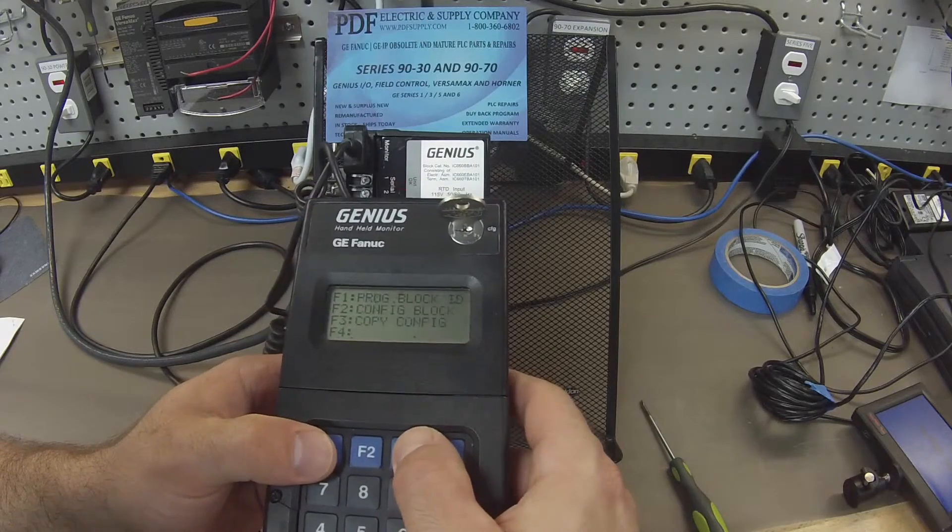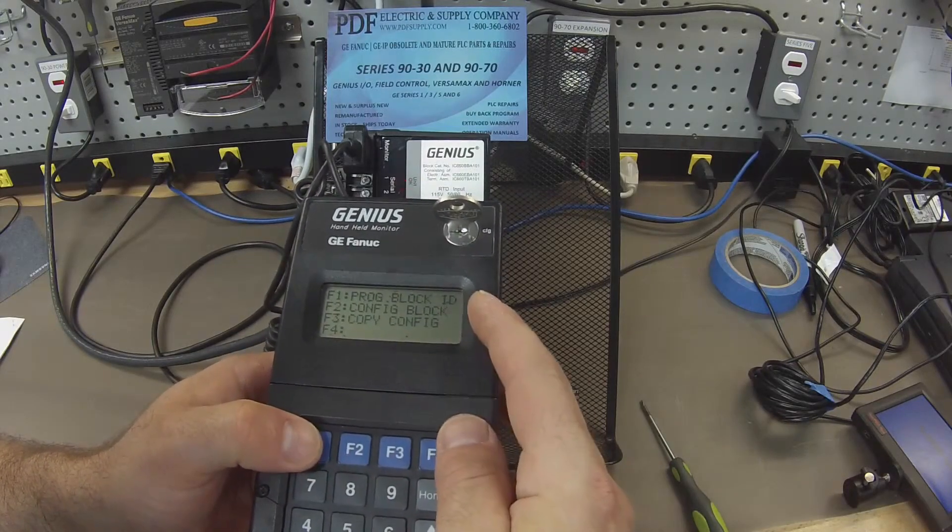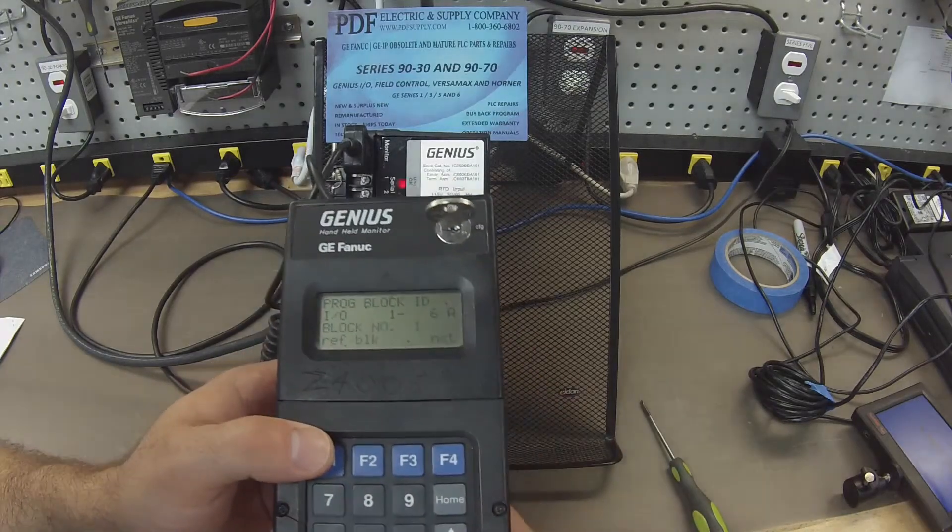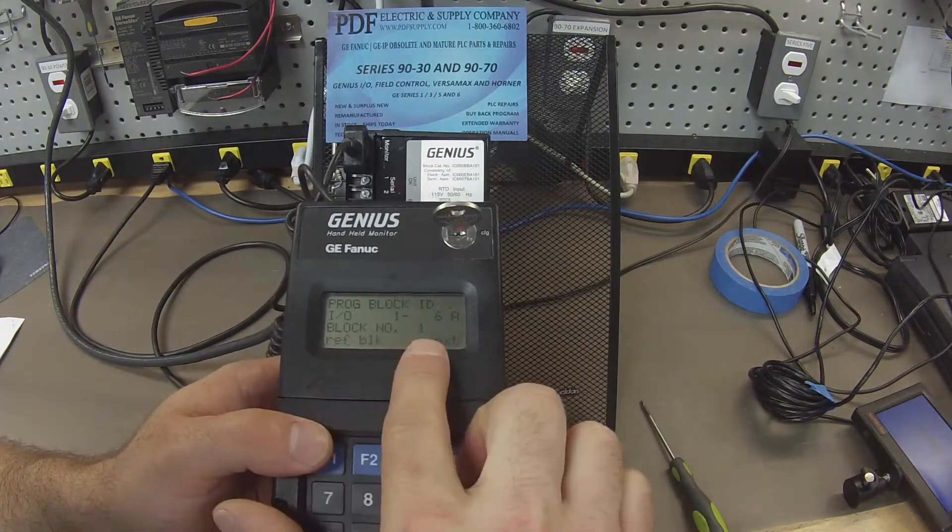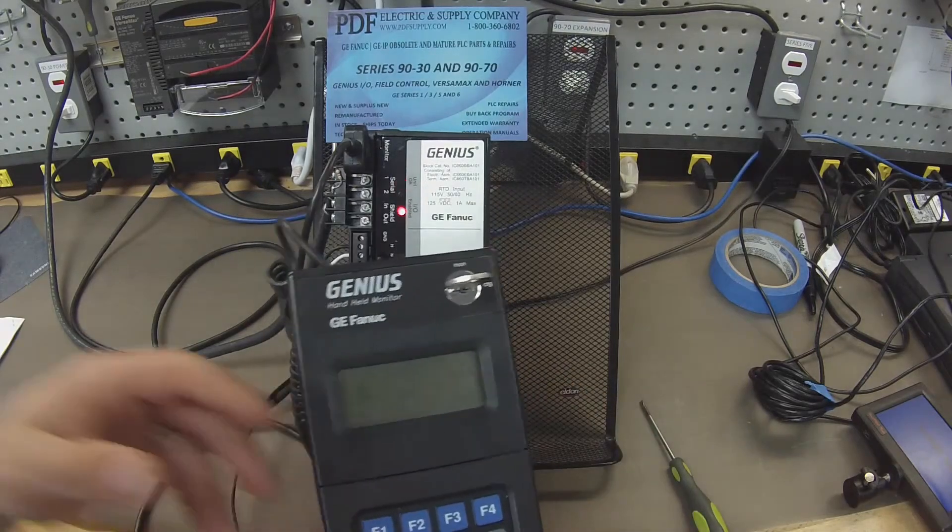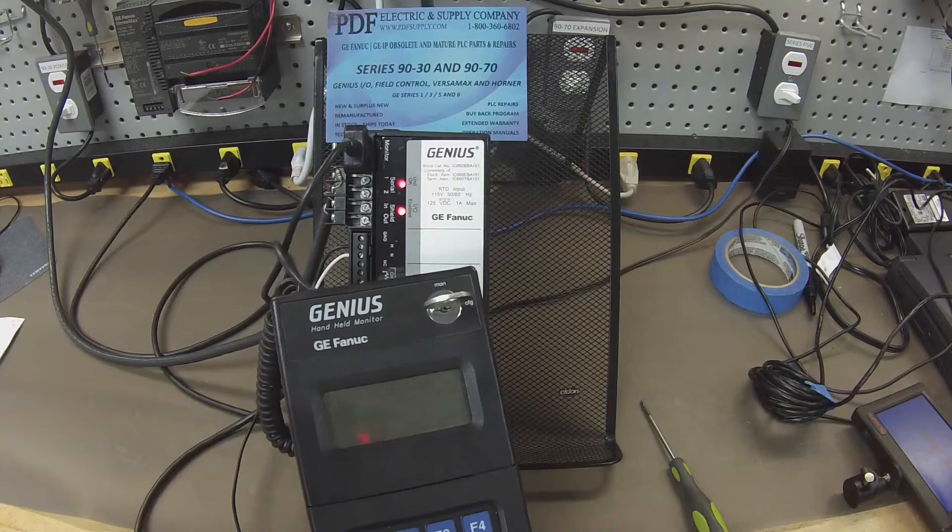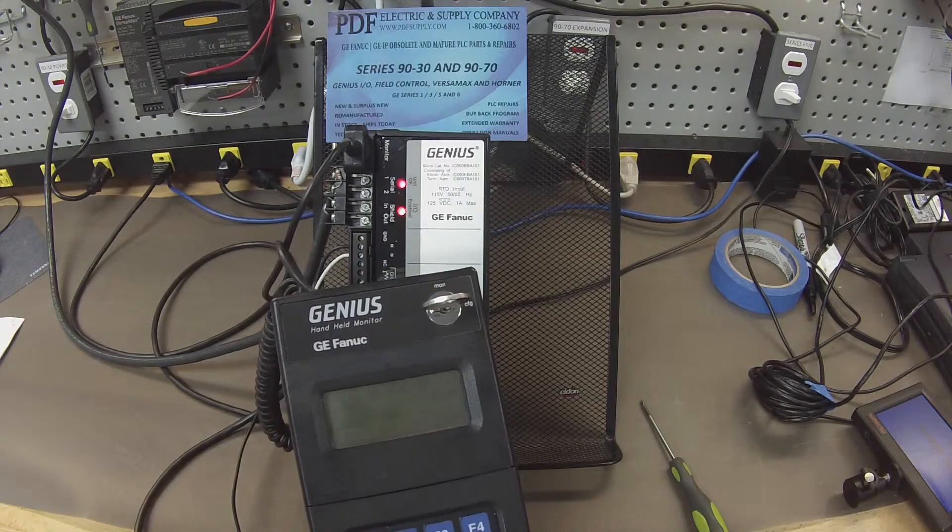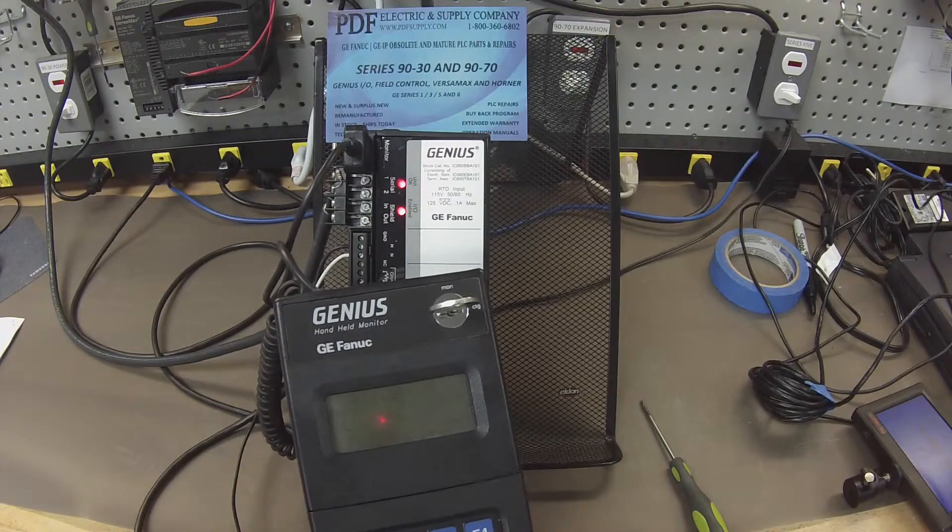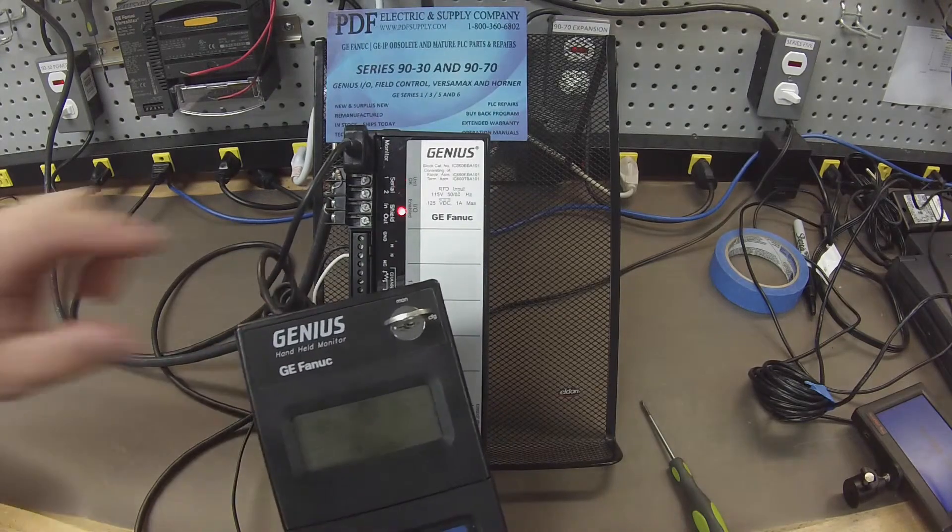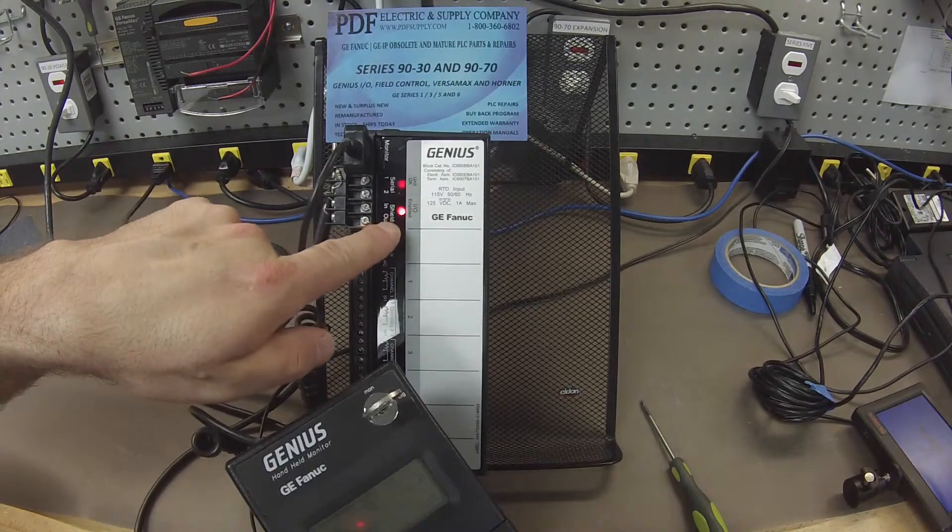Go to configuration F3, program block ID F1 and what I'm doing here is I've selected a block number that is the same as the block number that I've configured in Proficy Machine Edition. And the reason I do that is because when I get the software and CPU end of things in run mode it's able to turn on my I.O.